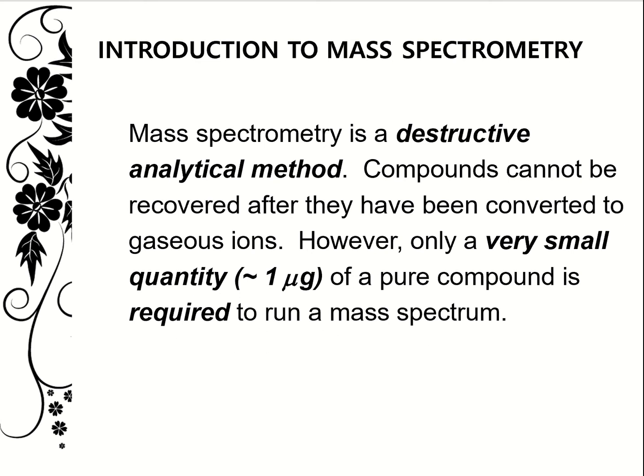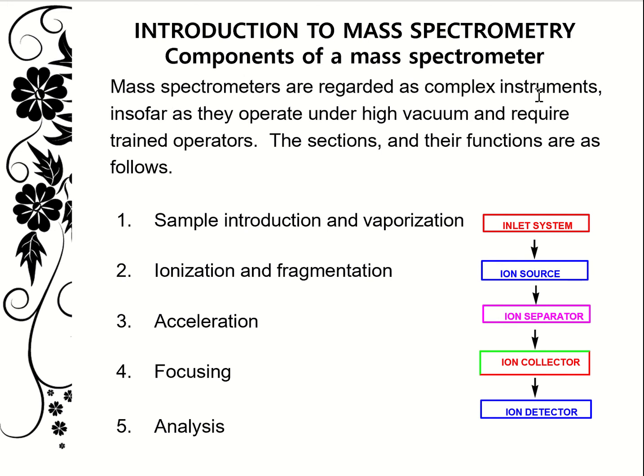While mass spectrometers are very complex instruments, we need a general understanding of how they work. They operate on high vacuum and require trained operators. The instrument has five components: sample introduction and vaporization, ionization and fragmentation from the ion source, acceleration, focusing and analysis, and finally ion collection and detection.